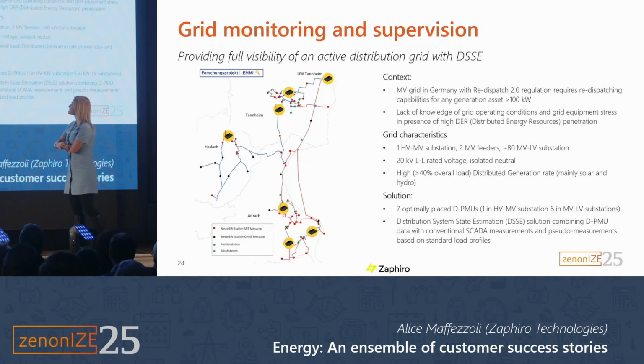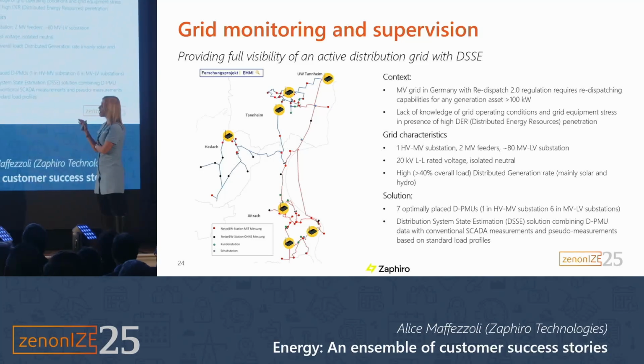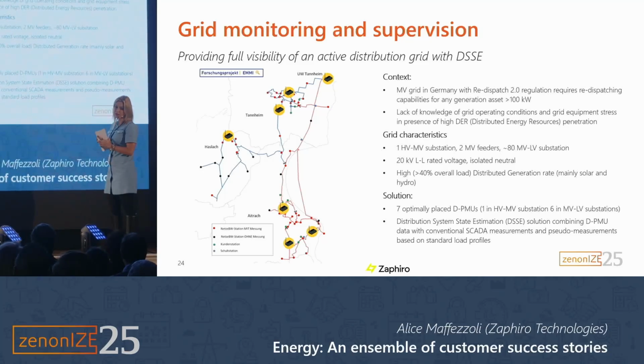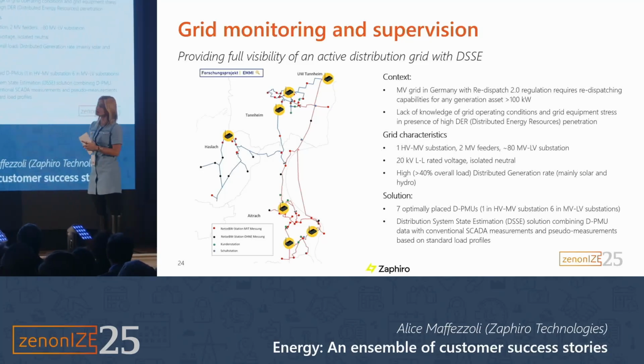Now, this is the most interesting part, I think, because these are real examples of what we have done. I will show you first an example of a client that was interested in observability. This is a German client. Here we have 1 high voltage to medium voltage substation, so 1 primary substation, 2 feeders with a total of 80 secondary substations. In this case, the interest was the integration, or rather the management of renewables, because the client was totally blind about what was happening in the grid.